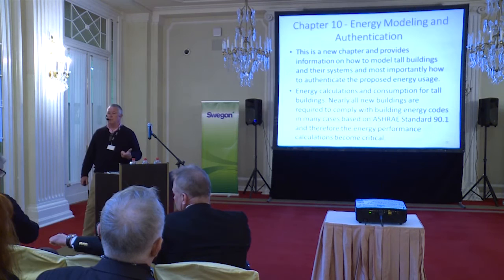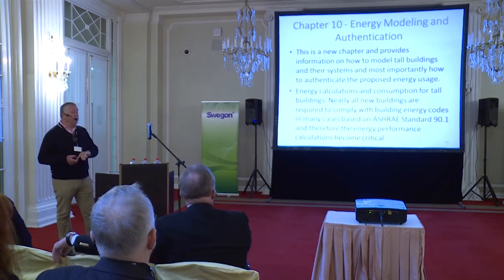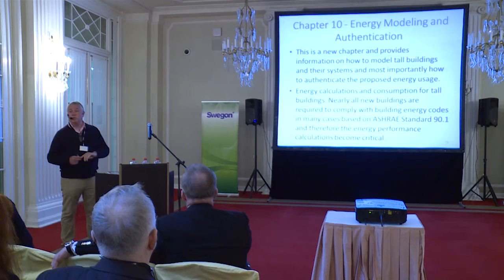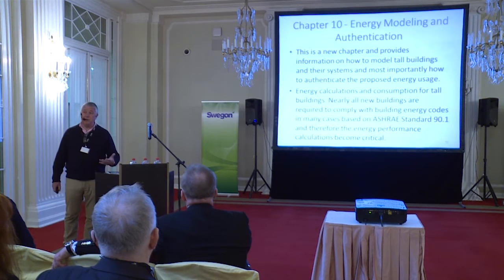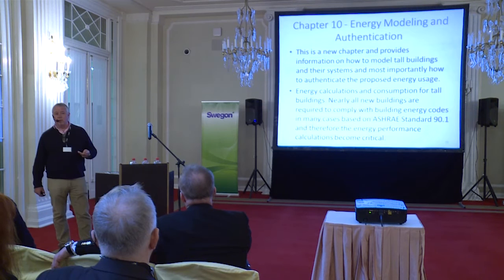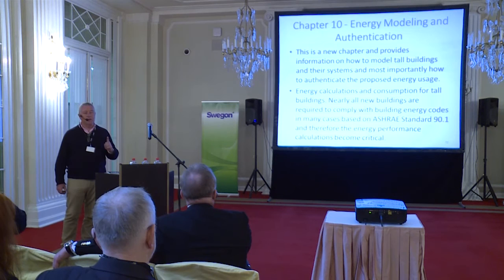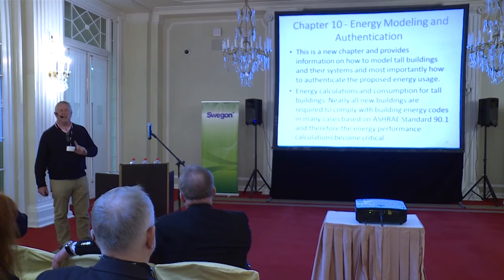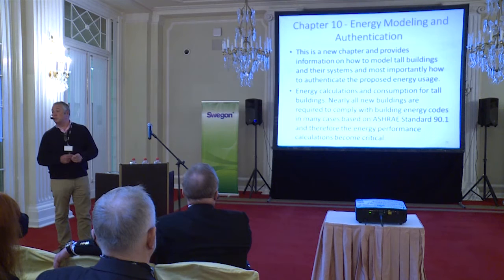There's a story going around, an American story from One Bryant Park, the Bank of America building. They looked at the energy use index and came out with a number: 317 kBtu per square foot. If you multiply that by 3.5, you get kilowatt hours per square meter, which meant it was more than 1,000 kWh per square meter, and it was supposed to be a LEED Platinum building. This is how corrupt the whole LEED system is. How can a building be LEED Platinum in the middle of New York City at 1,000 kilowatt hours per square meter? Can't happen. So who was right, who was wrong?